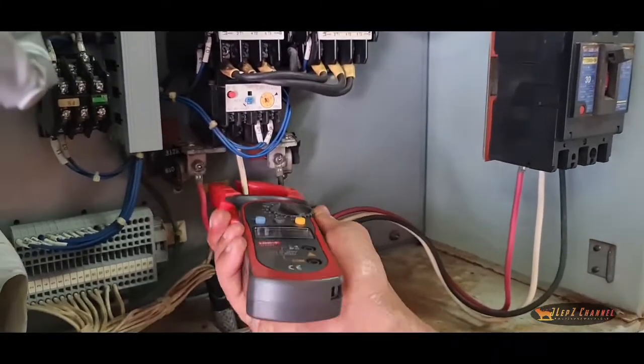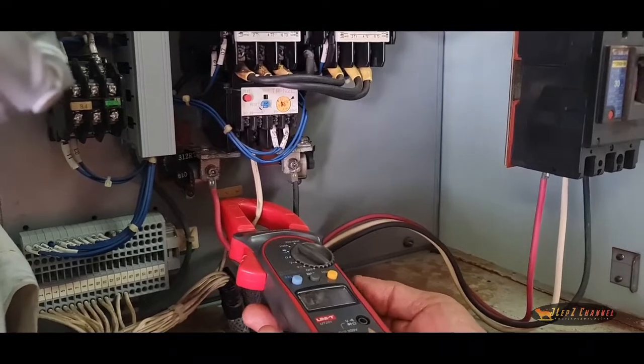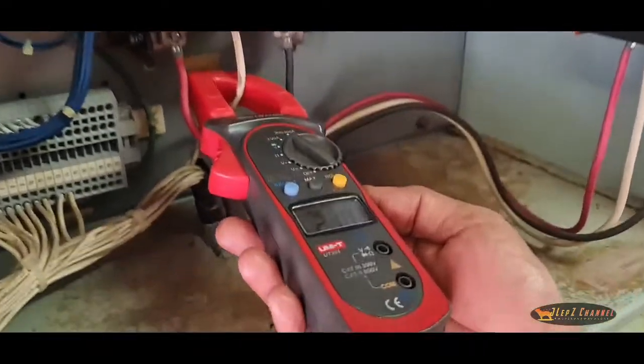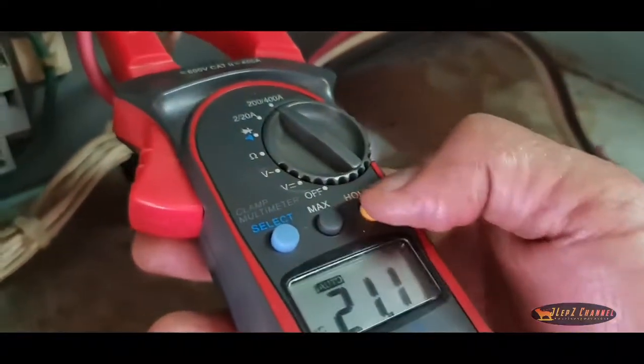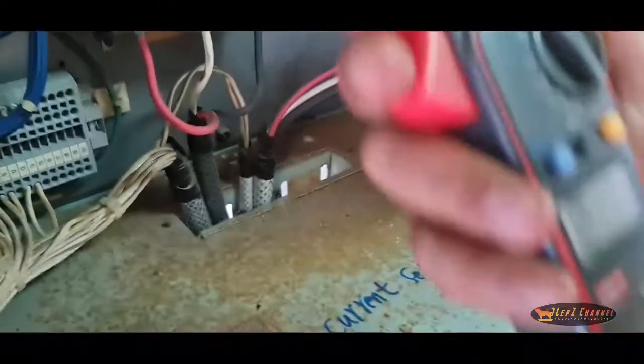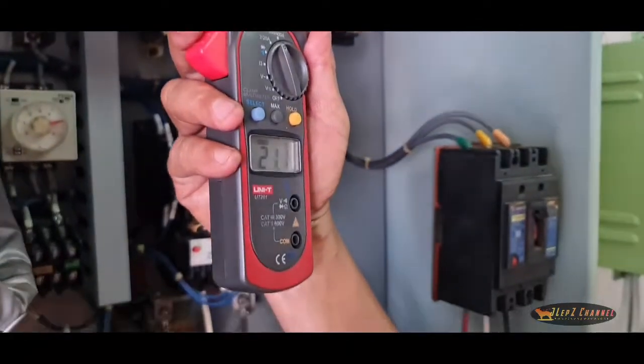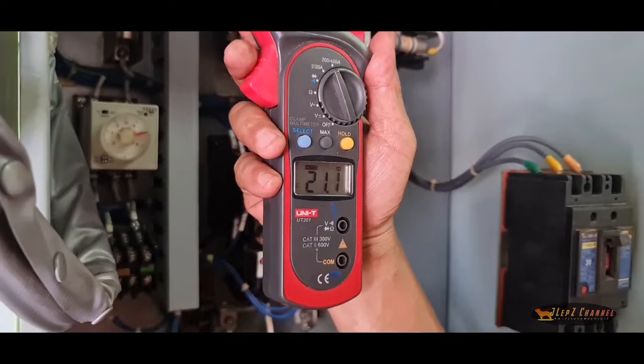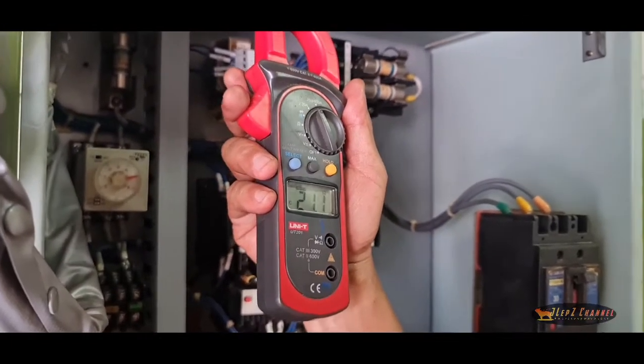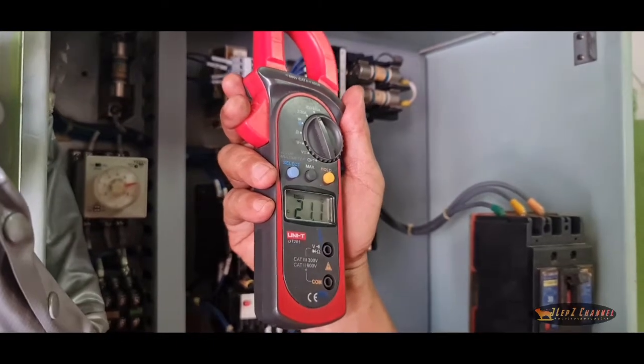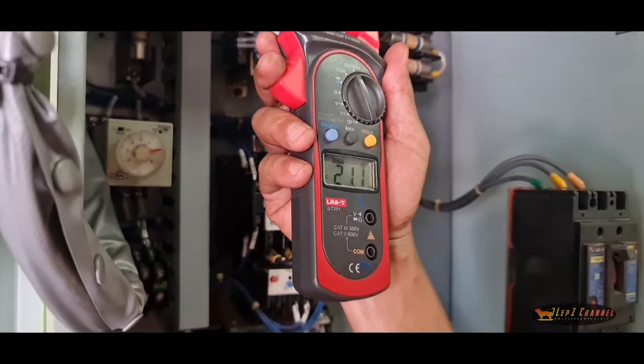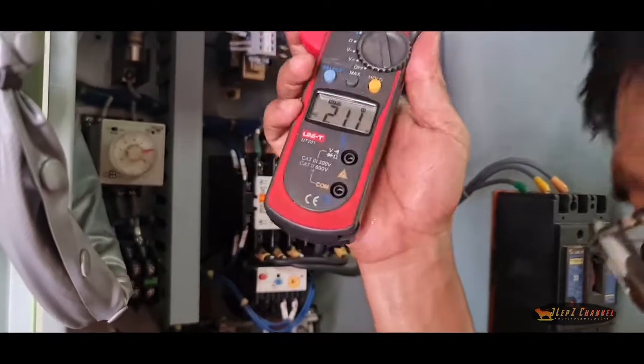So I will test again. Now I will press the hold, then you will see the reading. Previously that was 20.5. Now the reading is 21.1. So you see, that's the difference of not knowing how to use the clampmeter. You do not know that the load current is unbalanced. That is no good for the motor itself.